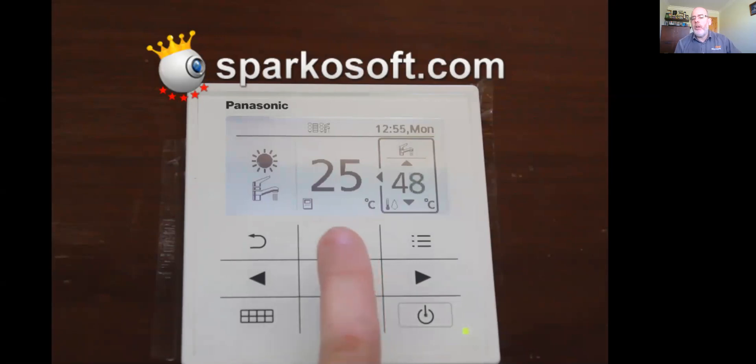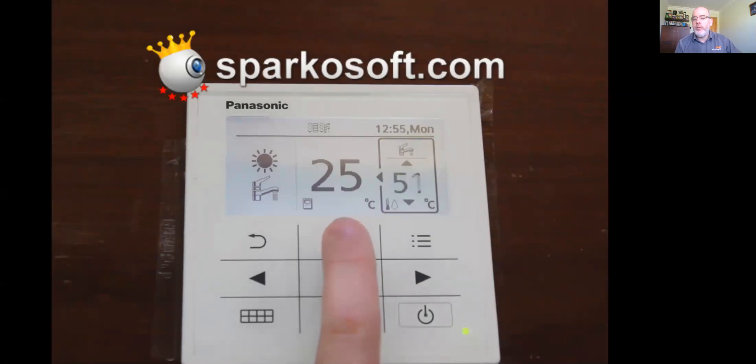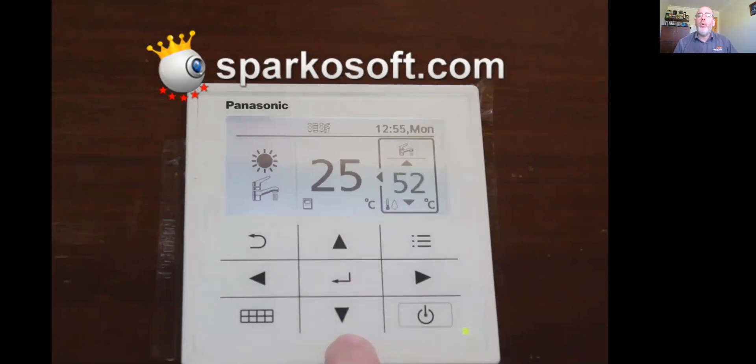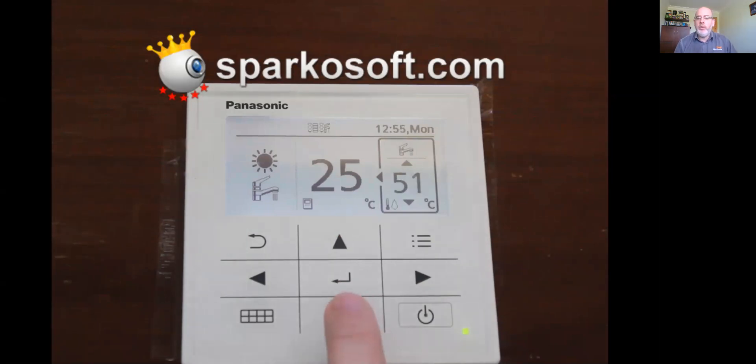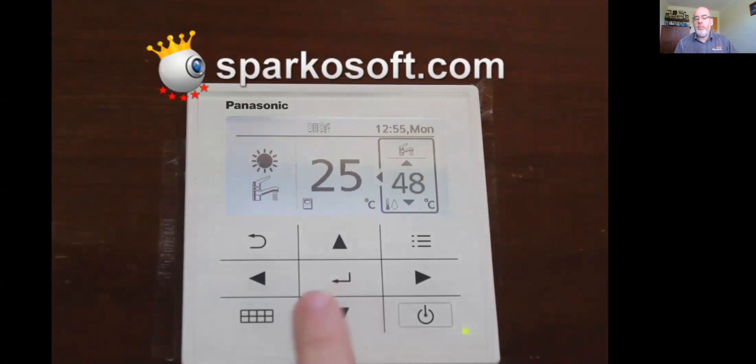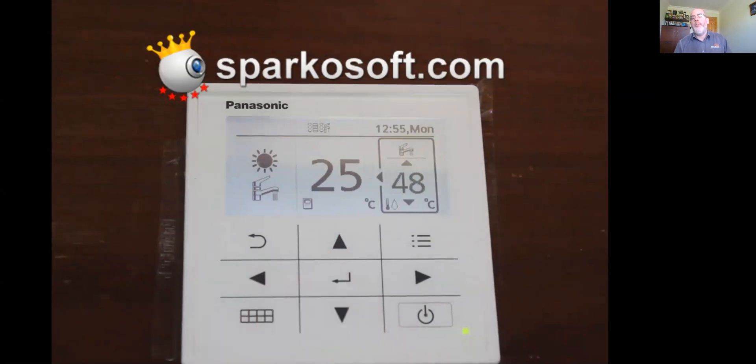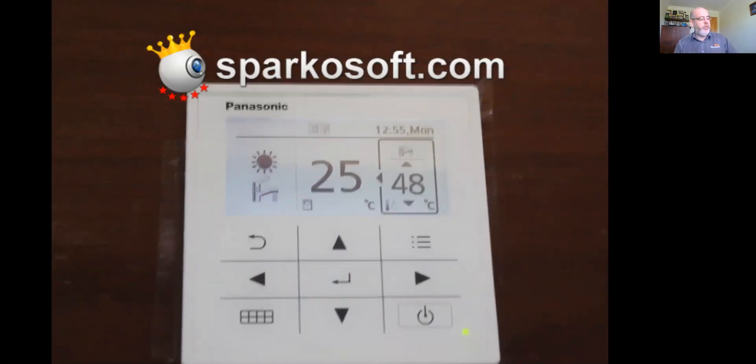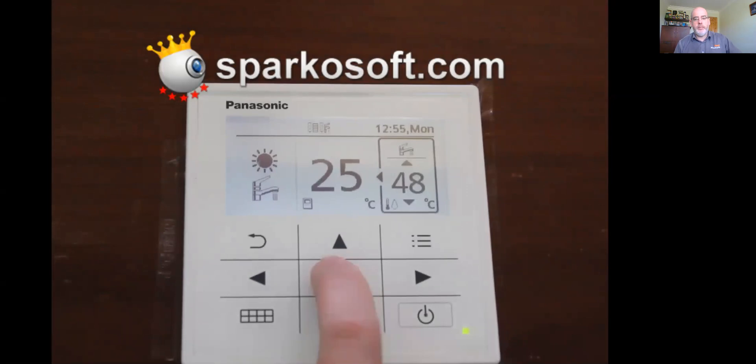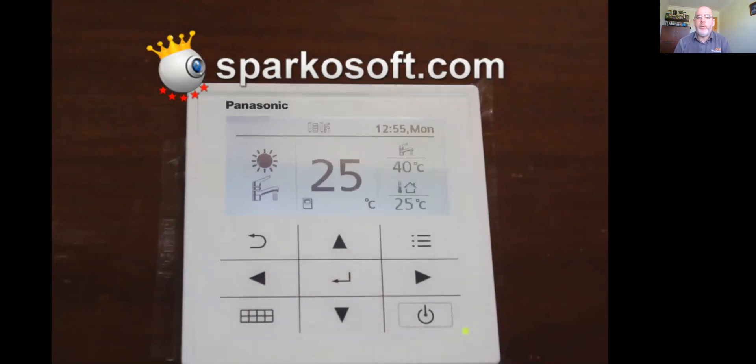I generally wouldn't put it above 48. You can go up to 49, 50, 51, 52, but you're just using more energy to give you the same result. So 48 degrees is basically what all the houses are set to and confirm. Once you confirm it, the screen goes back to normal.